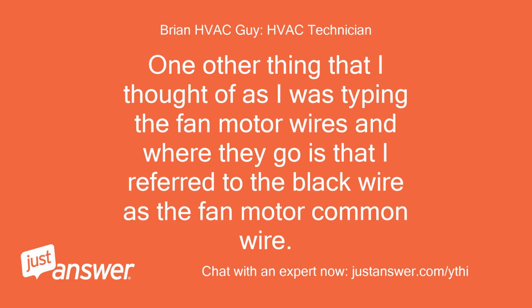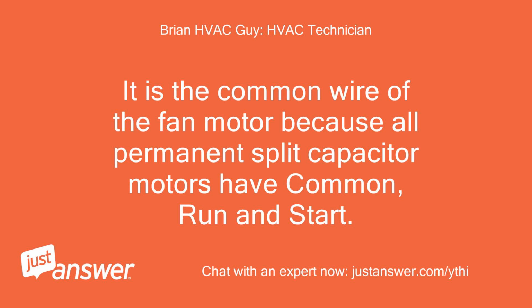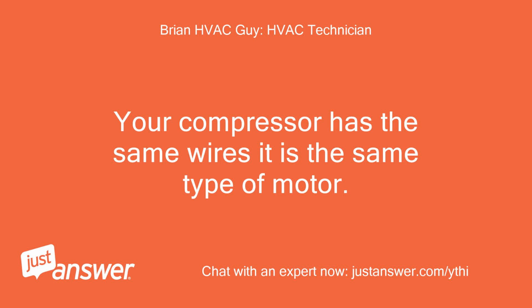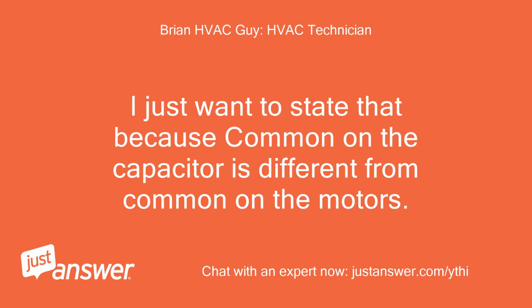One other thing that I thought of as I was typing the fan motor wires and where they go is that I referred to the black wire as the fan motor common wire. It is the common wire of the fan motor because all permanent split capacitor motors have common, run, and start. Your compressor has the same wires, it is the same type of motor. I just want to state that because common on the capacitor is different from common on the motors.